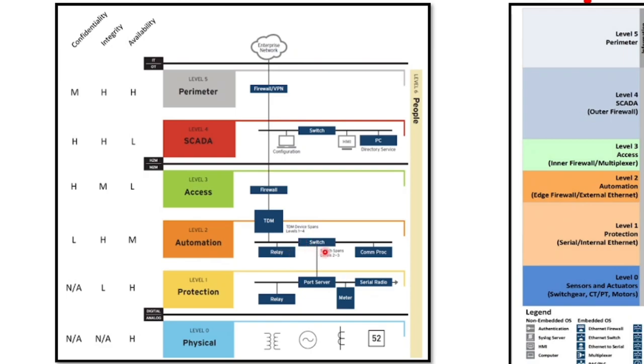At the automation level two, where relay switches and comm processors operate, integrity is the highest priority — any change at this level can disturb the process. Availability is medium because redundant systems exist. The proposed defense in depth model for ICS networks has multiple levels delineated by functional tasks and goals. Level three and below are machine-to-machine communications focused on ensuring continued operation of the ICS, while level four and above are human-to-machine with a focus on high-level services like data aggregation and data logging.